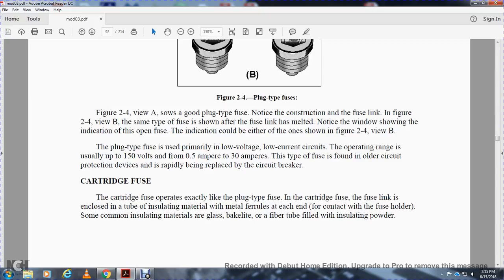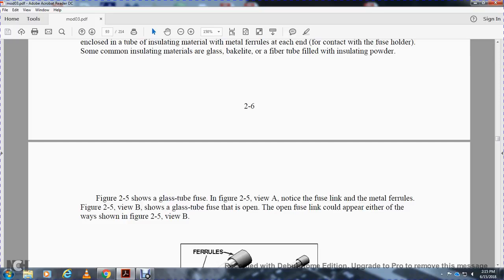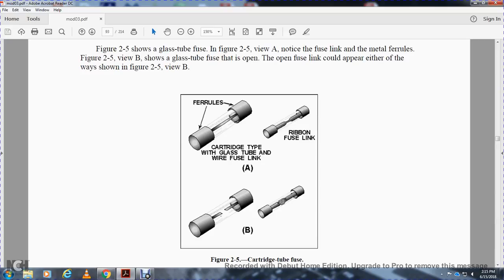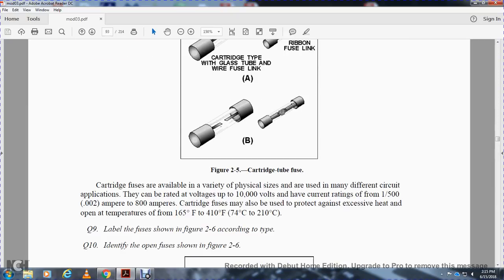The cartridge fuse operates exactly like a plug type fuse. The cartridge fuse has a fuse link inside a tube of insulating material with metal ferrules at each end for contact with the fuse holder. Some common insulation materials are glass, Bakelite, and fiber tube filled with insulating powder. Figure 2-5 shows the glass type. Figure 2-5, View A shows the fuse link with metal ferrules. Figure 2-5, View B shows a glass type fuse that is open - an open fuse link. Cartridge fuses are available in a variety of physical sizes and usually have different circuit applications. They are rated at voltages up to 10,000 volts and have current range ratings from 1/500 (.002) ampere to 800 amperes. The cartridge fuse may also be used to protect against excessive heat, opening at temperatures from 165 degrees to 410 degrees Fahrenheit.